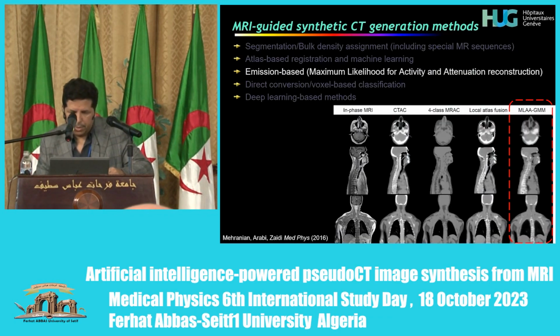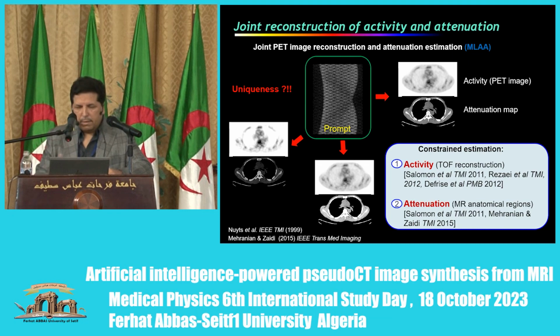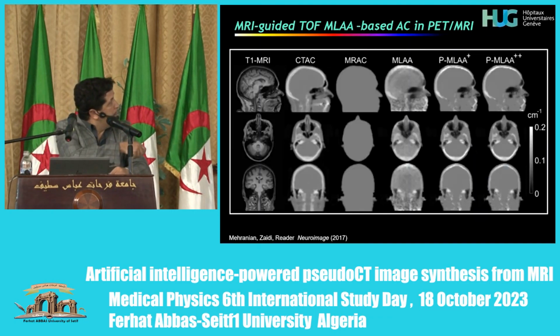The other category is what we call MLAA, or maximum likelihood reconstruction of attenuation and activity maps. So this is a very complex process that takes advantage of the high temporal resolution that we have on the commercial PET scanners, and provides a solution which unfortunately is not unique, in the sense that you have a scaling factor which is difficult to implement, and the generated attenuation maps using this kind of technique are very noisy, as you can see.